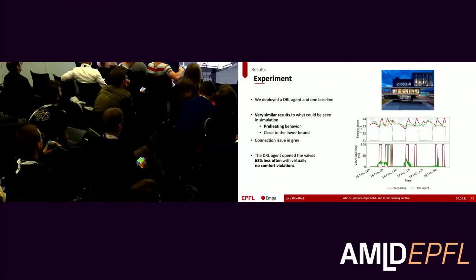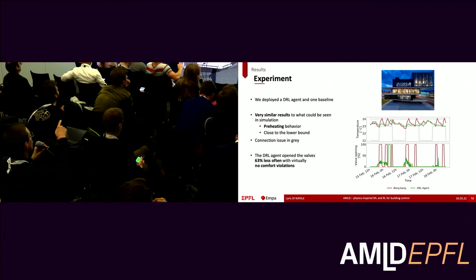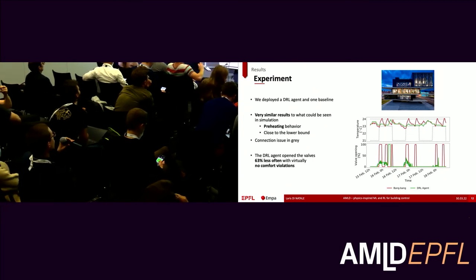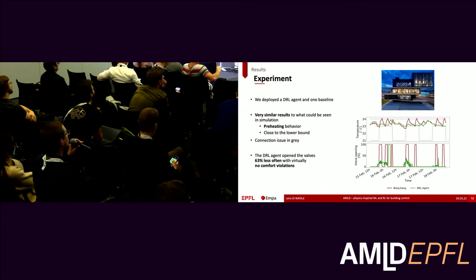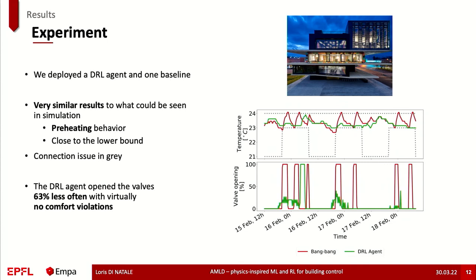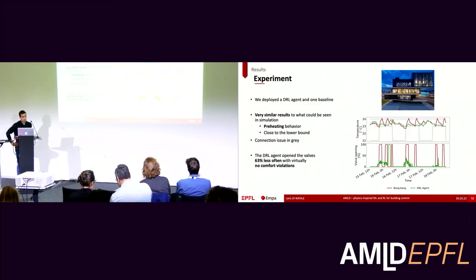Question: Do you remember what weather conditions you had during this real-building recording? Answer: Not really precisely — it was quite hot for February, with almost no heating required. It was also quite sunny, and you can see in the results that without heating the temperature is just rising because the sun is shining on the windows.